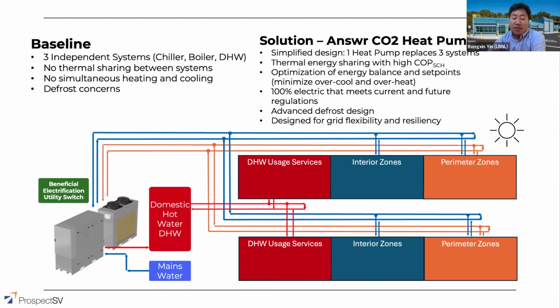For this project, I will use FLEXLAB to demonstrate the solution we propose, which is to use Answr's CO2 heat pump in place of existing heating and cooling plants. The baseline is clearly three independent systems: chiller, boiler, and domestic hot water plant. The point made here is there's no thermal sharing built into that system, it's just from the supply side point of view, not the demand side. I'm pretty sure there's some open space that has simultaneous heating and cooling load, but here we're just talking about the supply side.